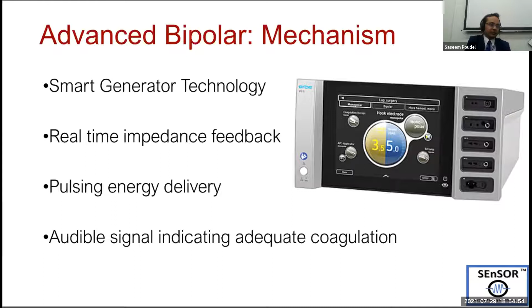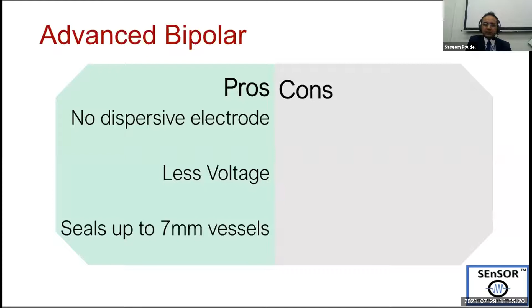And there are pros and cons of these devices. Since it's a bipolar device, it does not use any dispersive electrode, so current does not flow through the body of the patient. It also uses less voltage; most of these devices use around 200 volts or less. And it has the ability to seal vessels up to 7mm. But you have to remember that these machines also have lateral thermal spread of 1 to 3mm, which I'll talk about a bit later, and Dr. Sujit will be showing a video.